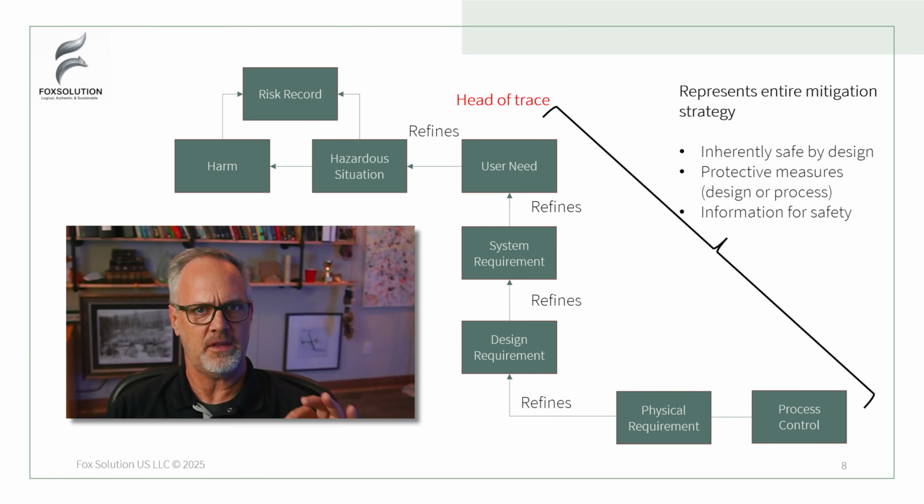So now each one of the hazardous situations has what's called a P1 factor. This is based on the 14971 risk management protocol, the appendix in that document. The P1 factor is how often that hazardous situation occurs. And that's carried inside the hazardous situation. This is the only thing really that we can adjust to mitigate the risk in our system. So we have a pre-mitigation P1 and a post-mitigation P1. Then when we pair the hazardous situation to harm, what we're going to get is what's called a P2 factor. And that P2 factor is how often the hazardous situation converts to the harm.